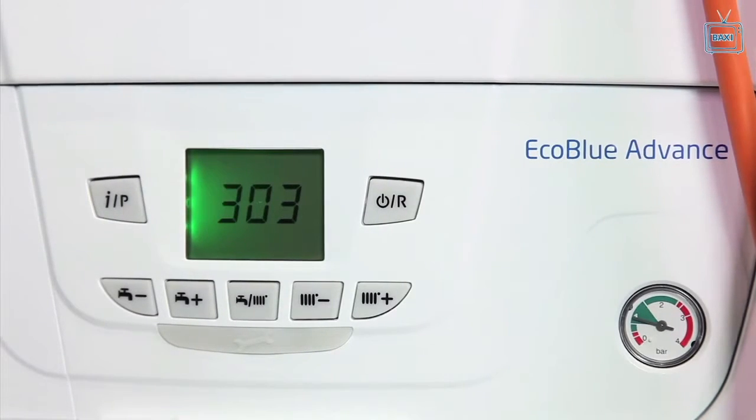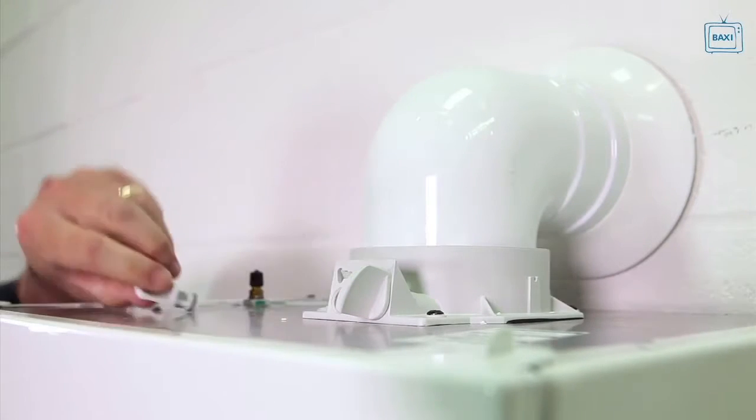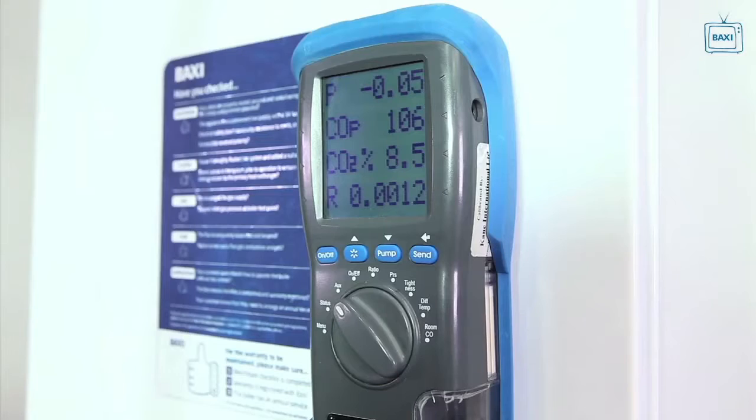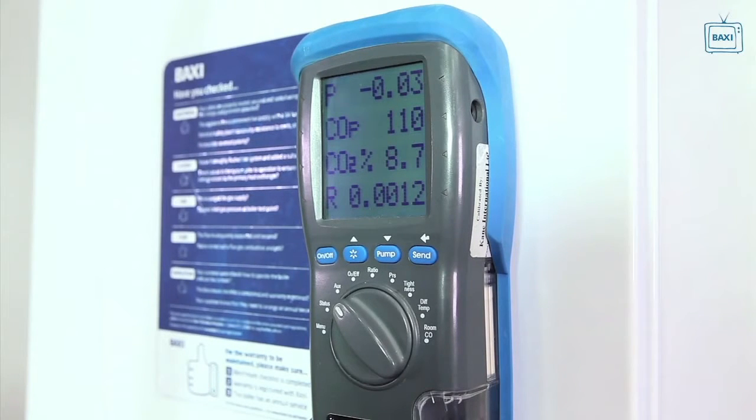Check the carbon monoxide and combustion ratio while the boiler is still running at maximum rate. Insert the analyzer probe into the flue gas test point. Once stabilised, a positive check will show a reading of 8.7% plus or minus 0.2%.